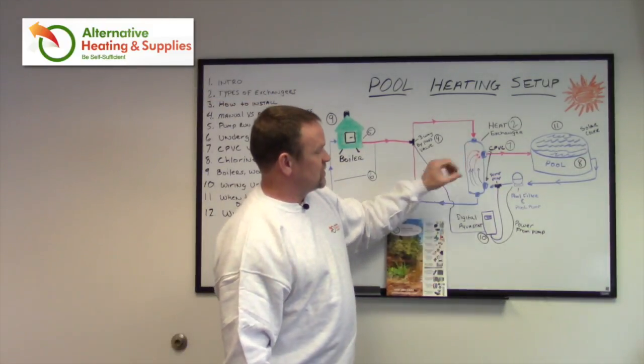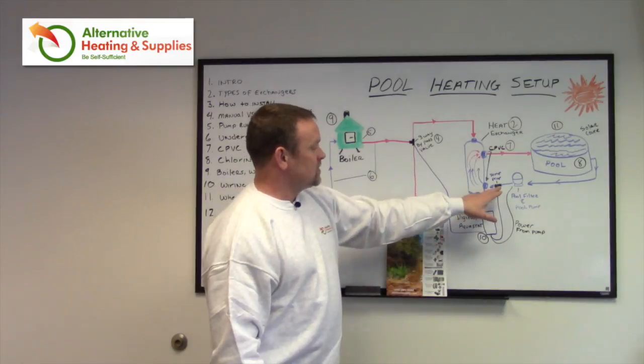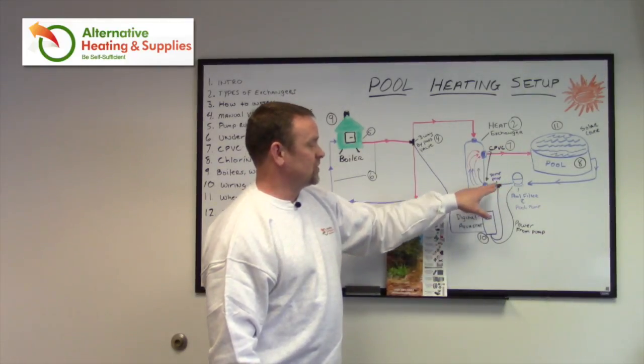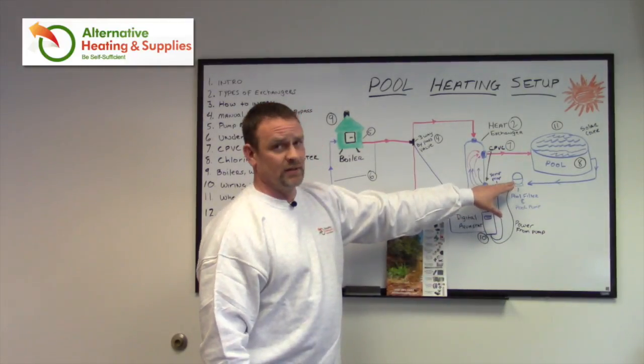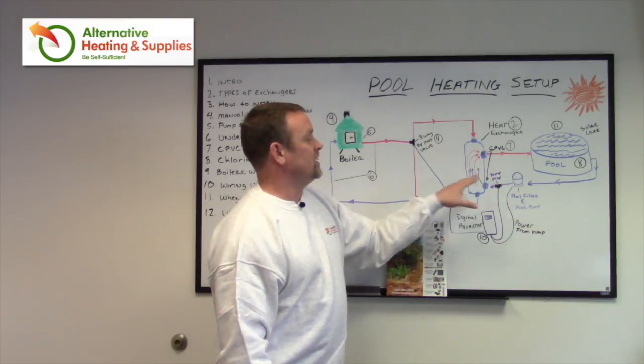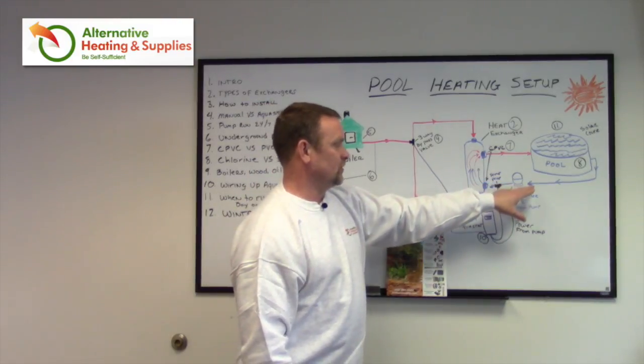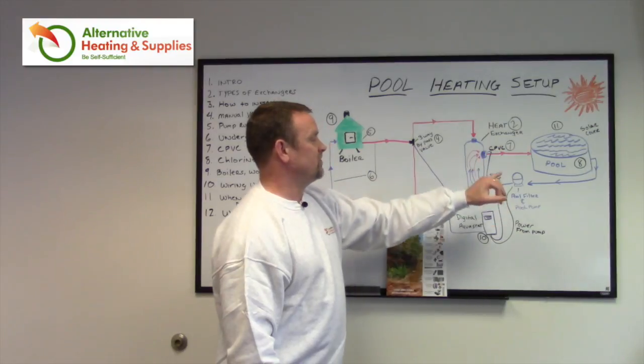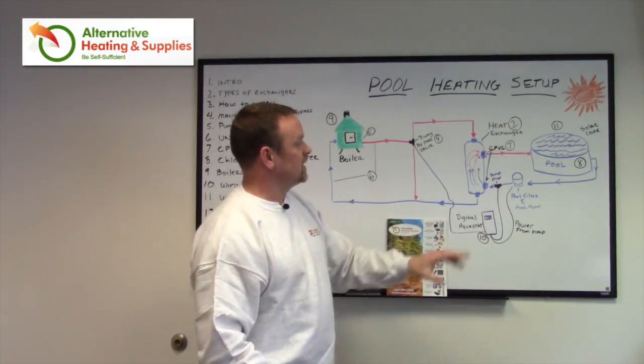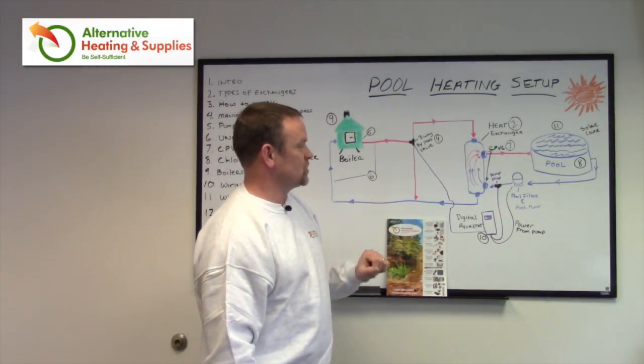So the heat exchanger sits there. In this process, we're also going to mount it after the filter and the chlorinator. You don't want it in front of the filters. You want the water to be filtered first, chlorination added, then into the tube and shell heat exchanger.